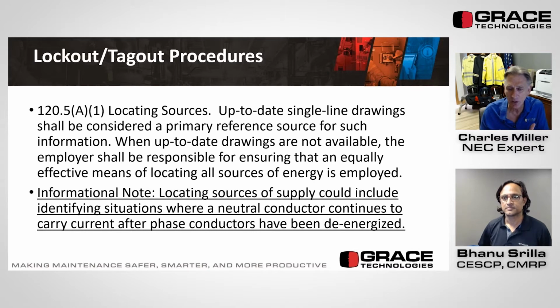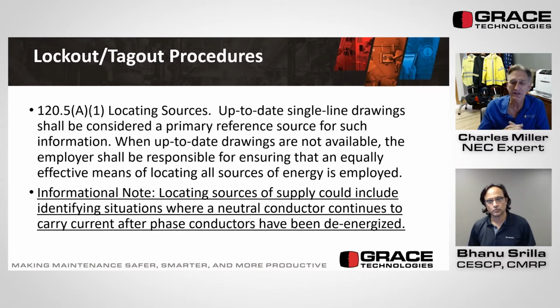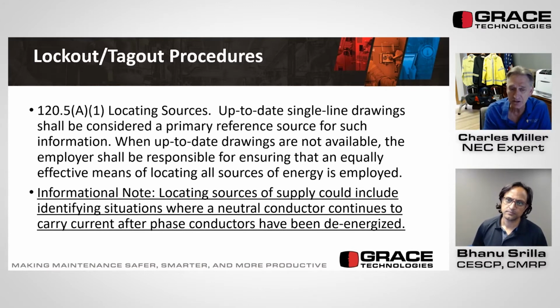in 120.5(A)(1), there's an informational note, and I think this was just moved down from the main text. Locating sources of supply. No, this is a new informational note. Locating the sources of supply could include identifying situations where a neutral conductor continues to carry current after phase conductors have been de-energized. Well, all right. So if it's a new facility within the last 3 to 6 years or so, or maybe even 9 years, then all of the phase conductors used for a multi-wire circuit, the phase conductors that utilize the same neutral, have to have a common trip handle circuit breaker. But before that, they didn't have to.